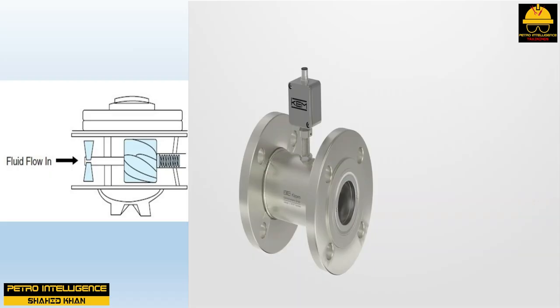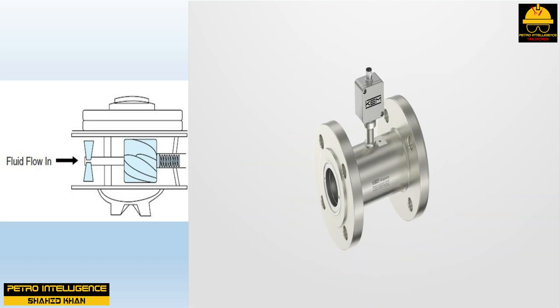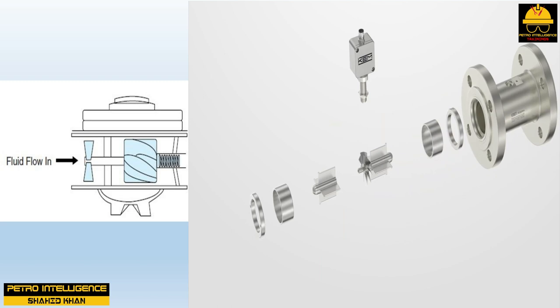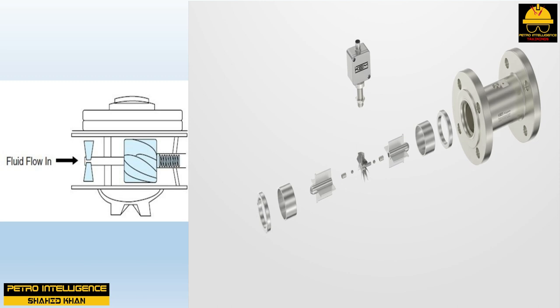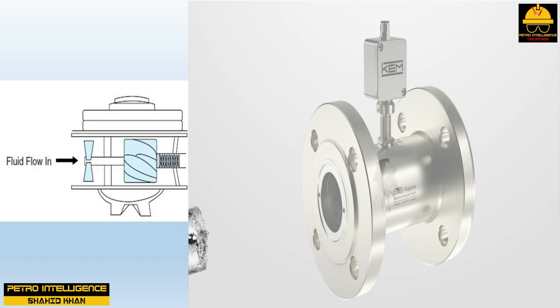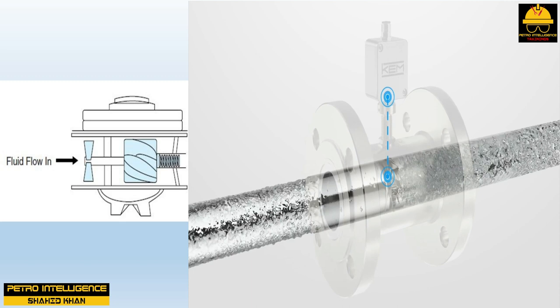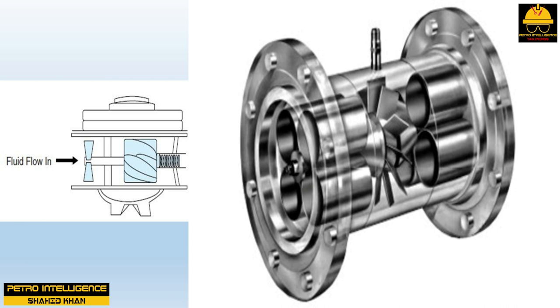Turbine flow meters usually consist of a section of pipe with a rotor mounted inside and a sensor on the outside. As fluid enters the turbine flow meter, the turbine blades begin to rotate; the speed of rotation is proportional to the velocity of the fluid. Flow velocity is the actual speed of the fluid measured as distance per unit time (e.g., feet per second), while flow rate is the total quantity of liquid passing a specific point measured as volume per unit time (e.g., gallons per minute). Turbine flow meters are accurate over a wide range of flows.